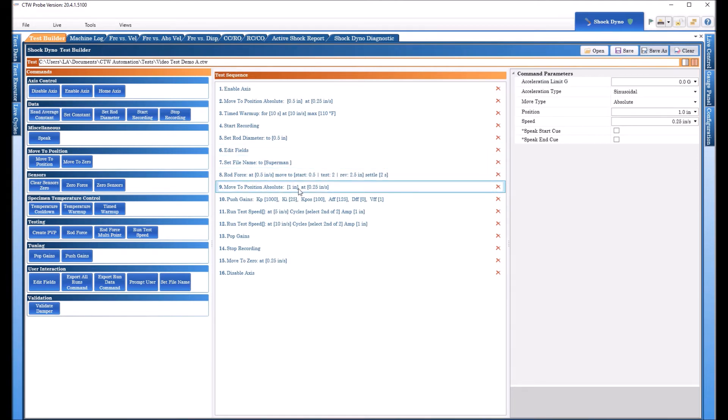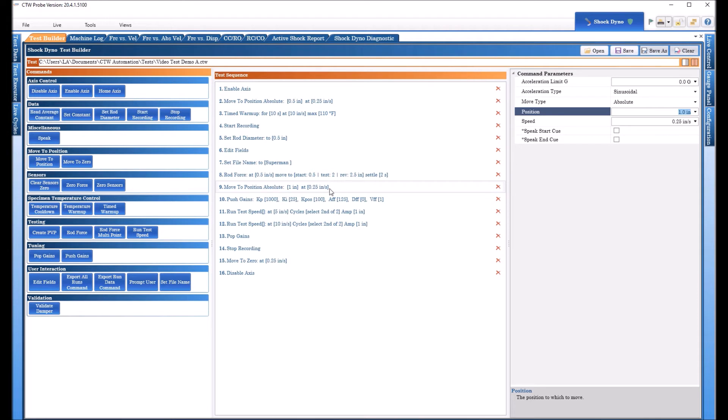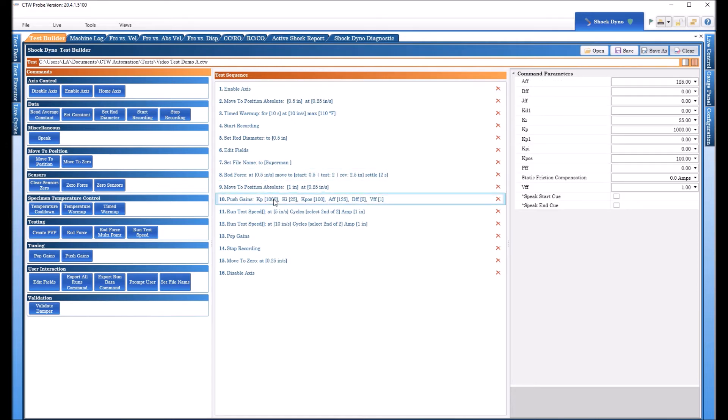When the rod force is done we want to say take this to one inch position so we can start our actual test. Now this is just arbitrary that's just a number I'm using you get to use whatever you want but basically your test will run from this position in the positive direction. So if you have a two inch stroke it's going to run from one to three and back in a sine wave. If you have a four inch stroke it's going to run from one to five so everything starts from this position and goes up no offset so that's very important.